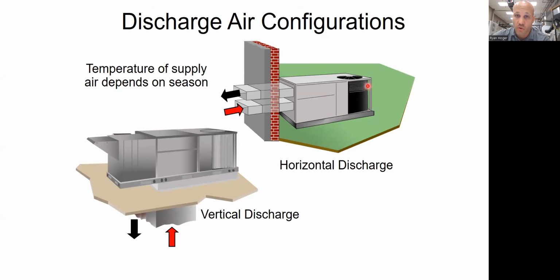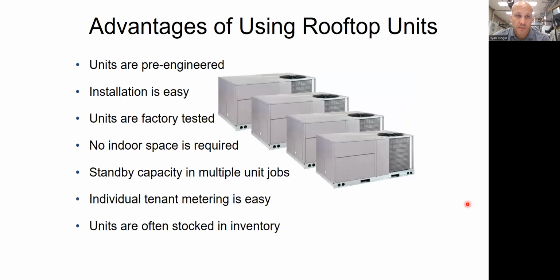As I mentioned earlier, you could also mount it on the ground next to the building, in which case we'd have a horizontal discharge, where the supply air discharges horizontally out of the unit and goes through the wall of the building and then ducts throughout the building from there. It is also possible to have things like a horizontal discharge and a vertical return and weird combos like that. But usually it's all vertical or it's all horizontal, but there are opportunities in certain applications to mix them.